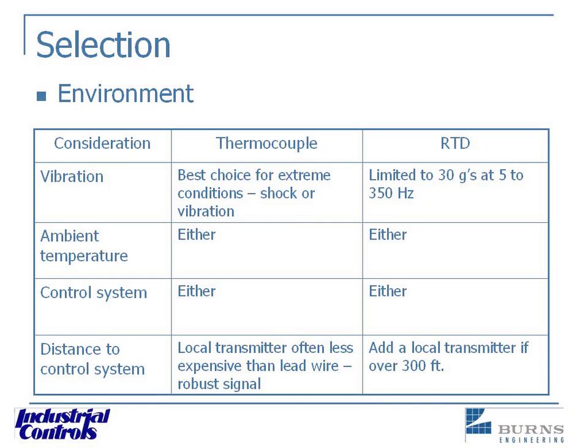Oh, okay, sure. What happens with an RTD in high vibration, especially the wire wound, is that the platinum wire starts to move a little bit within its potting material, and it can work harden and cause the resistance characteristics of it to change. And it's a very slight change, it might be only a few hundredths of an ohm, but that translates into a higher temperature change reading.